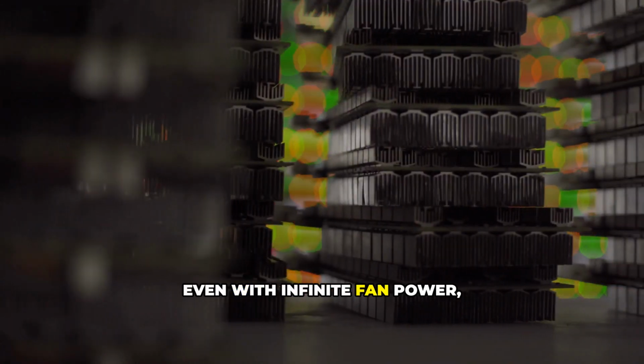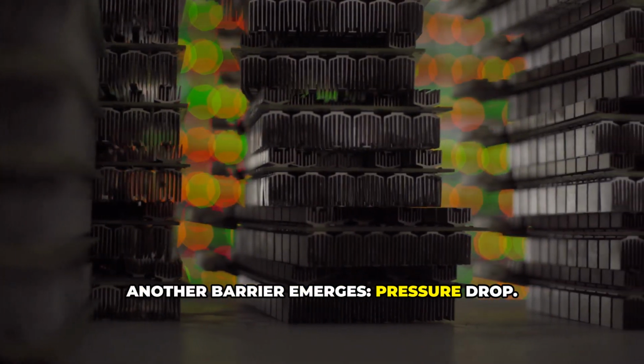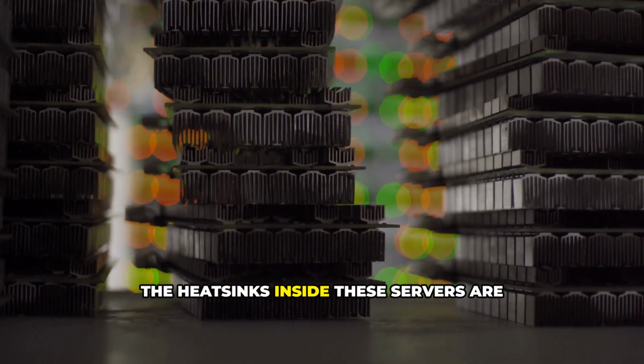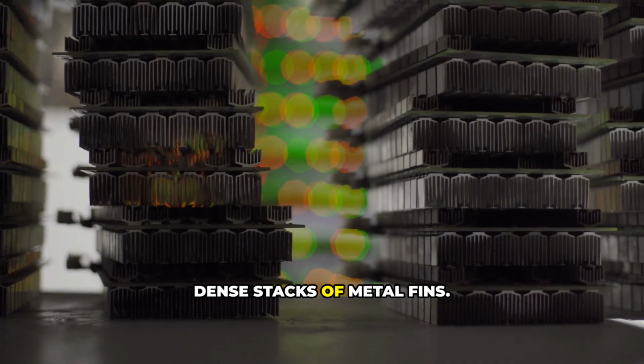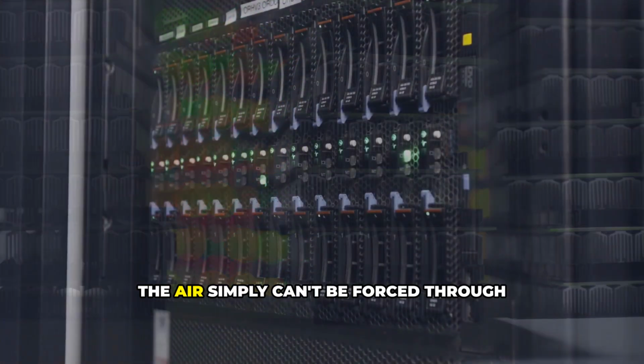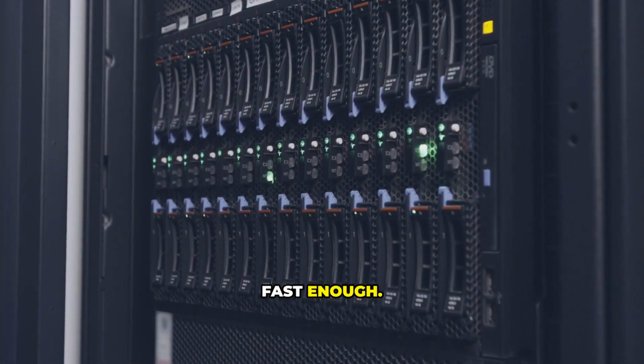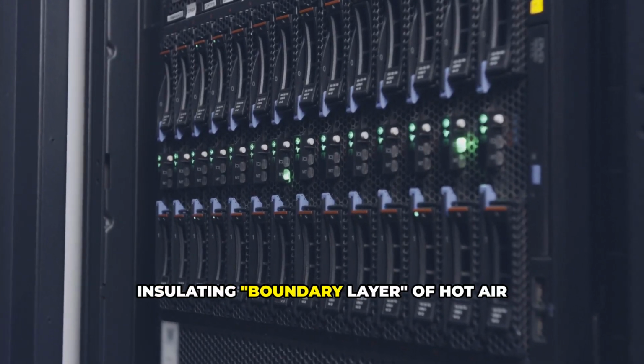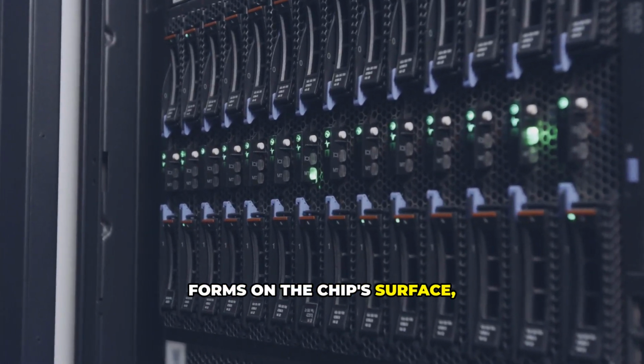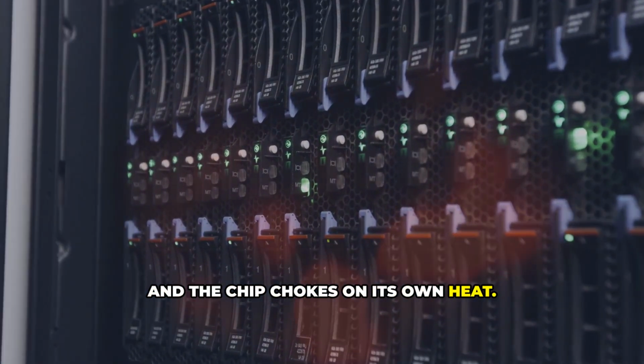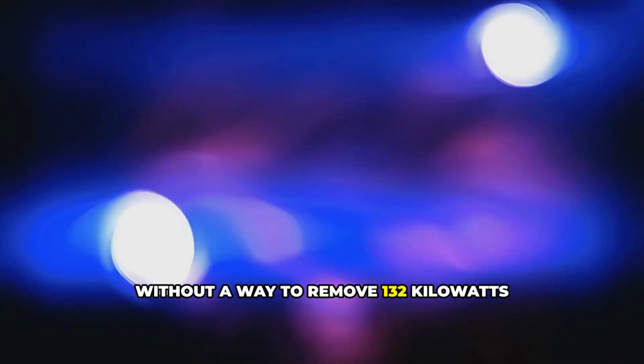Even with infinite fan power, another barrier emerges: pressure drop. The heat sinks inside these servers are dense stacks of metal fins. At a certain point, the air simply can't be forced through fast enough. A stagnant, insulating boundary layer of hot air forms on the chip's surface, and the chip chokes on its own heat. Without a way to remove 132 kilowatts from that cabinet, the system cannot run at its full potential.